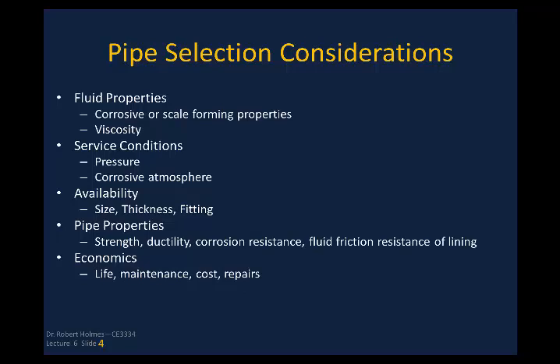Then there's service conditions: what kind of pressure are you going to encounter? Is the atmosphere going to be corrosive? How about the availability of what you're buying — the pipe you're specifying in terms of size, thickness, and fittings? Can you get it readily available where the cost is not prohibitive to truck it a long way to your building location? How about the pipe properties: strength, ductility, corrosion resistance, friction resistance, and lining? Here in the lab at the campus, we've been doing some testing for a pipe manufacturing company, trying to nail down the effective roughness of the pipe itself.